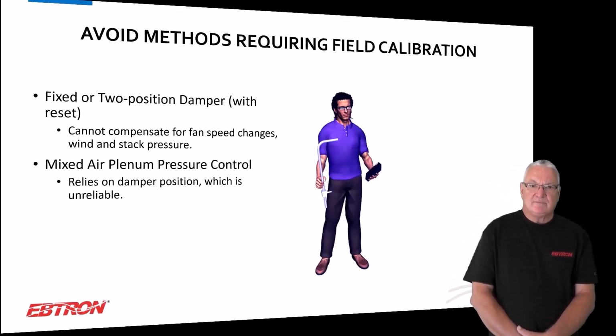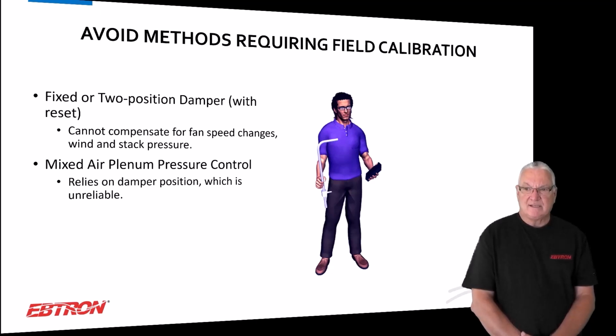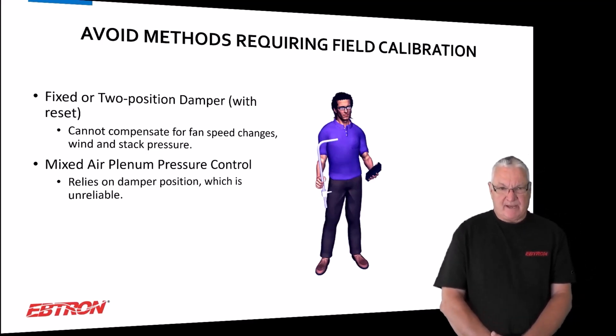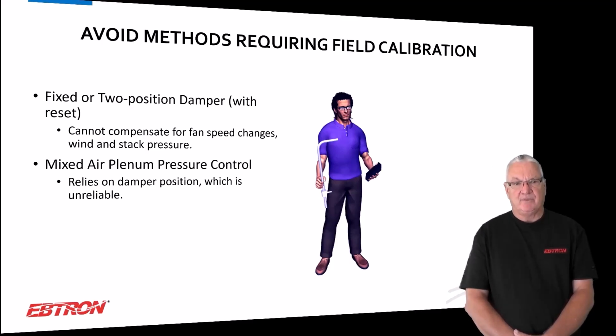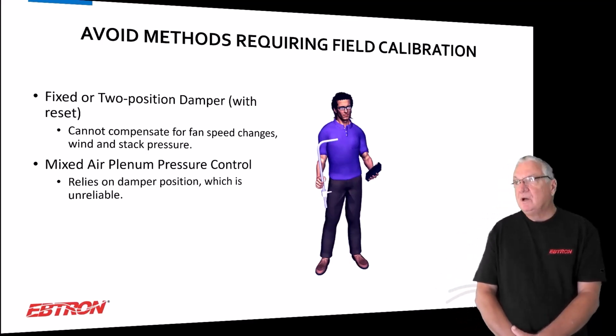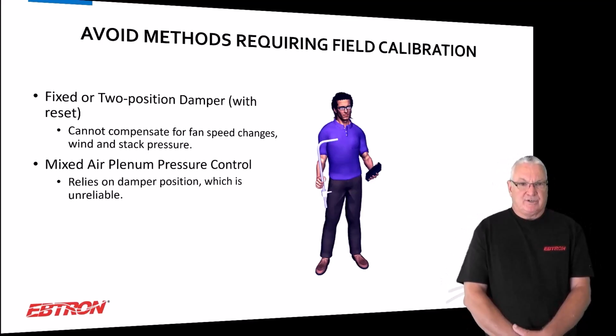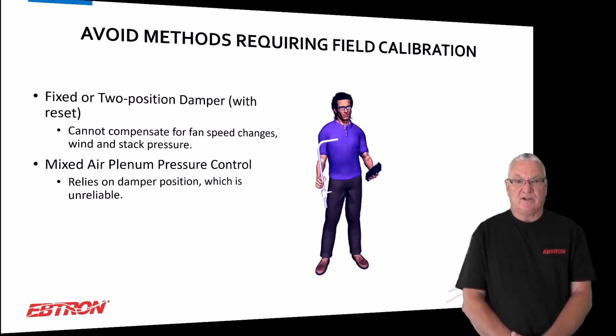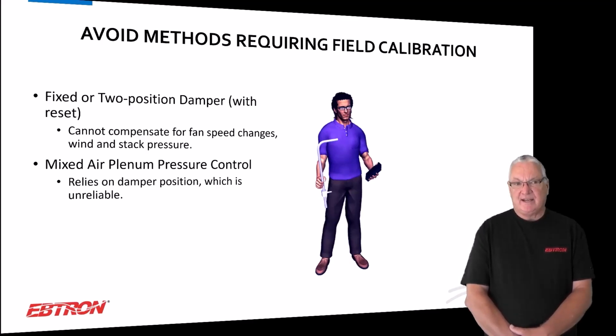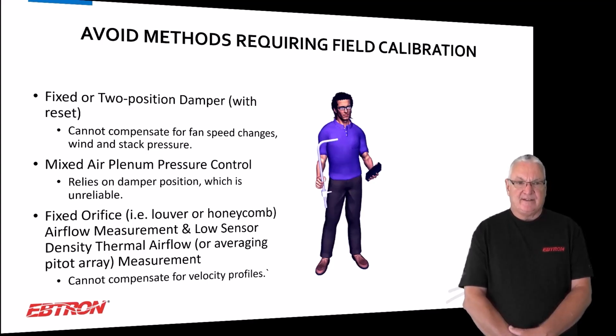Mixed air plenum pressure control, though, is something that people do try to do. What is that? I'm going to maintain the mixed air plenum pressure constant. Some people do it to the mechanical room, which is a really bad idea. Other people put it across the damper, which is a better idea, because then you're getting some component of wind and stack pressure. But the problem is it relies on damper position, and there's no way to know if the damper has problems, the things we talked about regarding damper: hysteresis, binding and deterioration. It's also pretty hard to control. So there's no real positive verification of flow. The only thing you have a positive verification of is that you've maintained this pressure drop or pressure point. So I'm not a real fan of that.